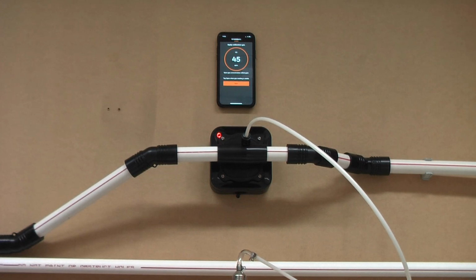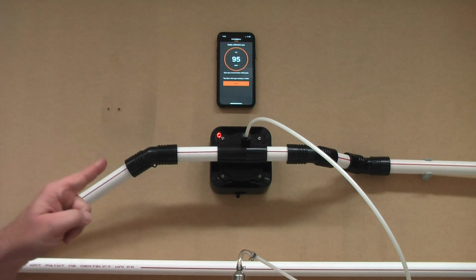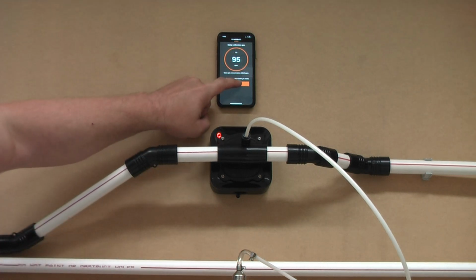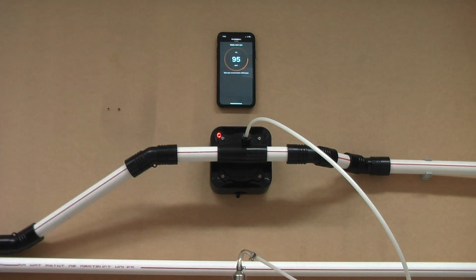You can see at this stage the detector is registering the gas. So I hit the span button now as the reading is stabilised, and the detector will apply the span reading. Okay, so the span reading is passed.